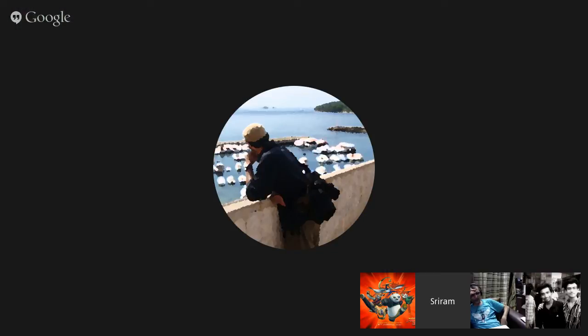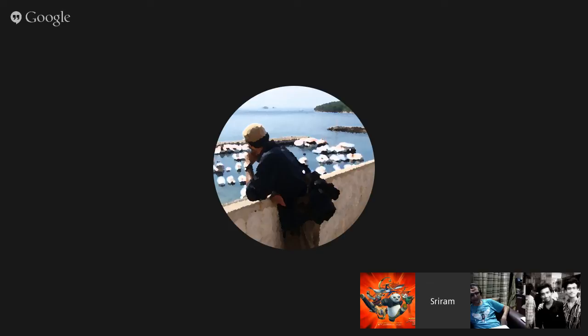Ambient light - wouldn't that affect any of these sensors you're using? Unless you have data otherwise. Luckily, the baffles used to absorb ambient light and prevent its ingress are quite good. But in outdoor conditions where you have light pollution, it does skew the readings. For which particular sensor? For all of these sensors, if you place them in ambient light - we haven't tested it out, but they generally say you shouldn't. Ambient light is definitely a factor in providing accurate readings.